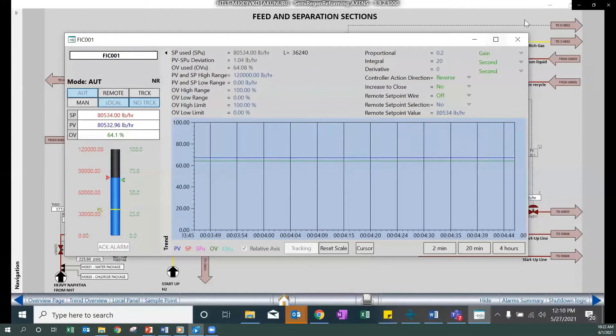When in manual, the output value can be changed, and when in automatic mode, the set point can be changed. When you click on this button, it expands the faceplate on the right, giving the trainee a trend view of the controller values, as well as the option to edit the controller tuning if necessary.